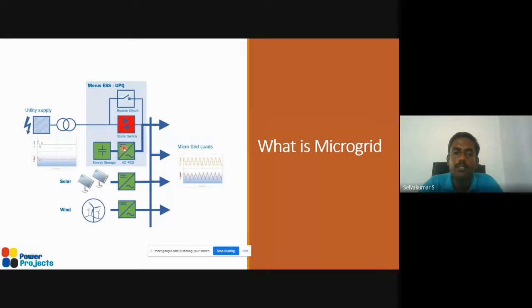So here the battery energy storage system provides an amazing option to compensate whatever mismatch there may be between real power and reactive power generation, to maintain voltage and frequency. In addition, this sets the voltage reference even in absence of a grid - even if the grid fails, this sets the voltage reference so that there's no interruption in the solar and wind generation. If it's available, it can generate power.